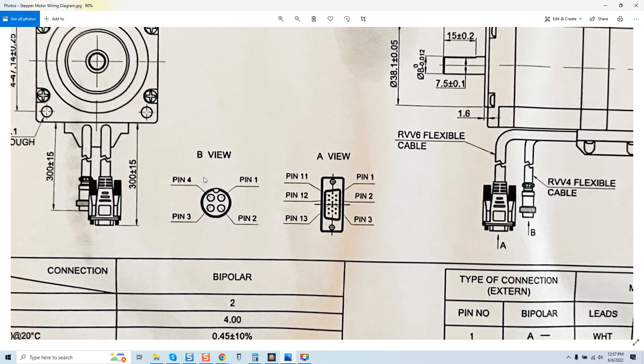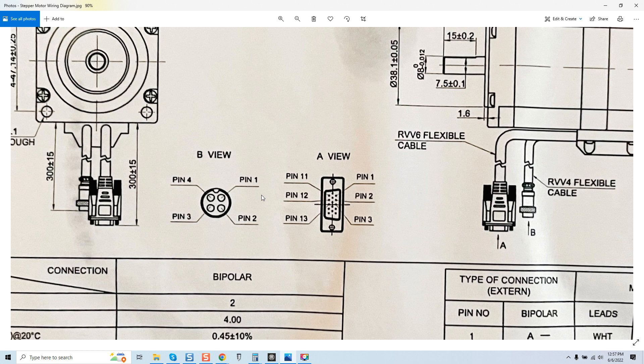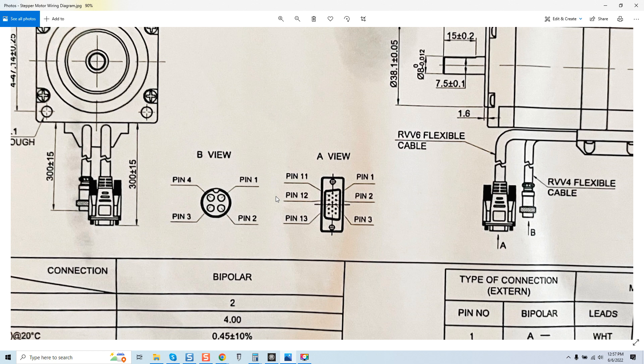The other major point you can see here on the B view this is the connector to supply the motor power. You can see it's a four pin connector GX16. The issue with this is that a GX16 four pin connector does not have a shield drain. There's no allocation here for a shield drain. None of these cables are shielded and they should under best practice be double shielded regardless of them having an encoder.